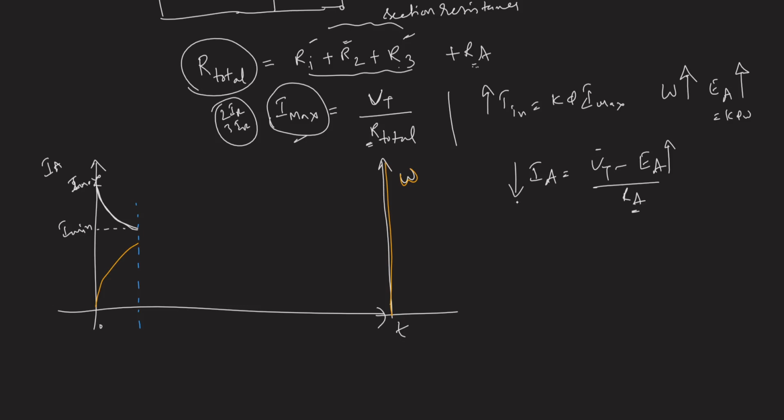Initially, when I first place onto the stud 1, it goes to the I max, let us say 2 times of rated current. Then speed rises, armature current comes down. So when it comes down to, suppose I say I minimum is equal to rated current, and this is 2 times of rated current, right? So I know the rated value of the machine, 200, 300, 400. So I know 2 IR, and I know the IR values.